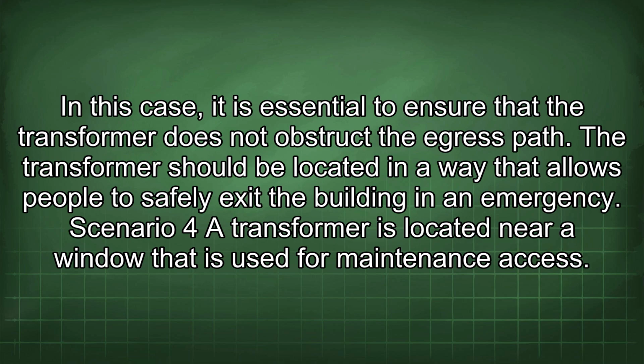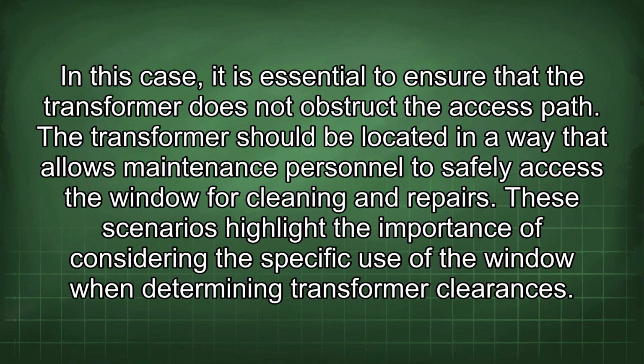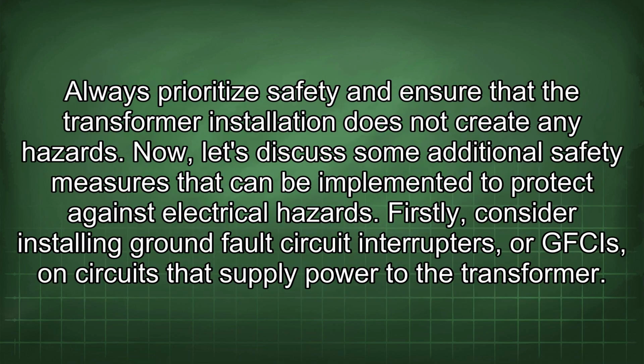Scenario 4: a transformer is located near a window that is used for maintenance access. In this case, it is essential to ensure that the transformer does not obstruct the access path. The transformer should be located in a way that allows maintenance personnel to safely access the window for cleaning and repairs. These scenarios highlight the importance of considering the specific use of the window when determining transformer clearances. Always prioritize safety and ensure that the transformer installation does not create any hazards.